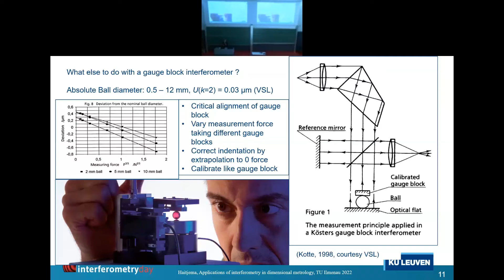And then you may think, yeah, but you have a measurement force, you have indentation. Yeah, that's no problem. Then we just take different gauge blocks. If it's twice as long, it also has twice the amount of weight. And you can measure the indentation. And here you see our measurements of the indentation. And you can extrapolate to zero force, and you have a nice calibration of the ball diameter. And the uncertainty which is delivered today is 0.03 micrometer. So it's not so bad at all. So it's one of the alternatives you can still do with a gauge block comparator.